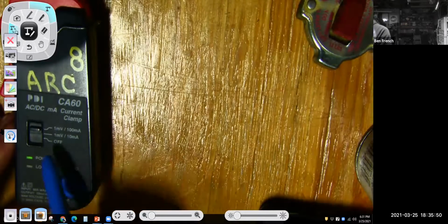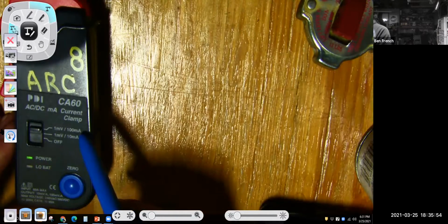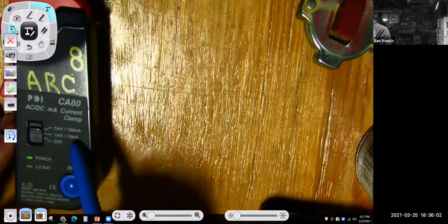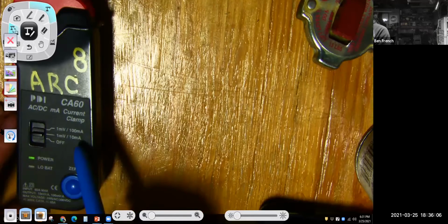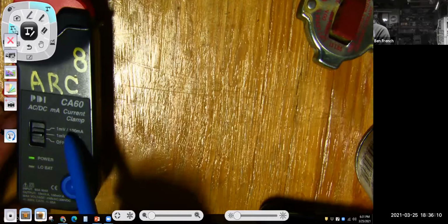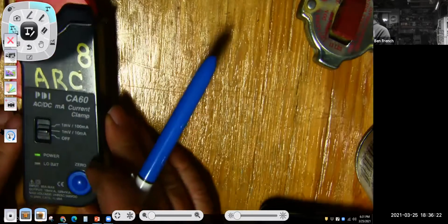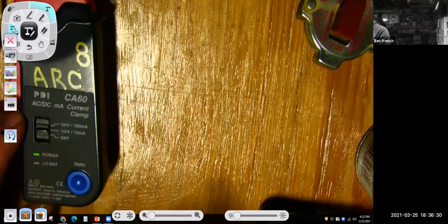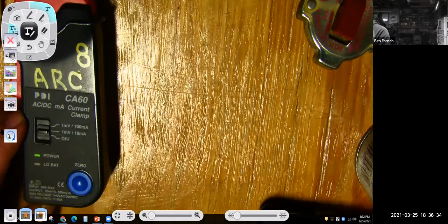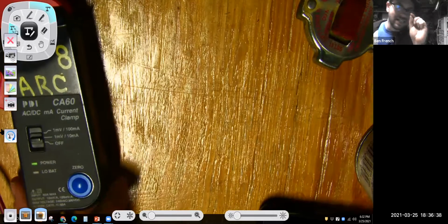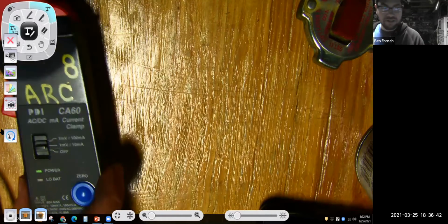Let me zoom in and refocus here. On this setting, for every 100 milliamps it measures, it will send to your multimeter 1 millivolt. On this other setting, for every 10 milliamps it measures, it sends the meter a reading of 1 millivolt. So it converts the magnetic field at the tip into a voltage reading, and based on the scale you have it set on, it tells you how many amps are flowing through that wire. Your meter is set to measure volts, so you have to realize you're actually measuring amps because you're using your current clamp.